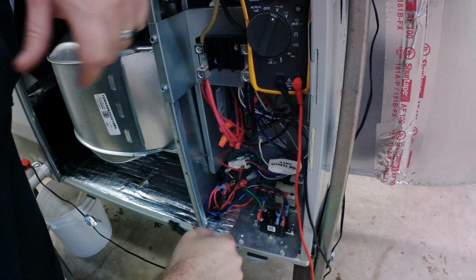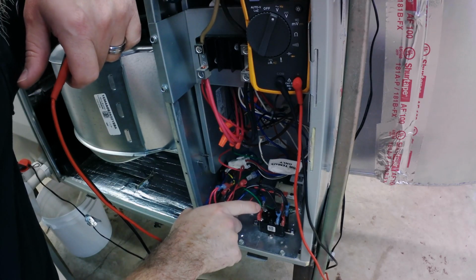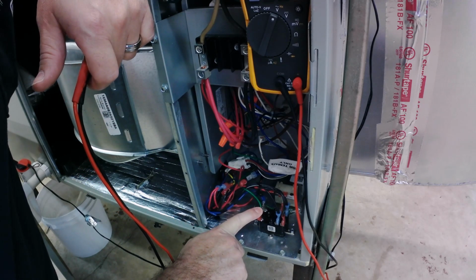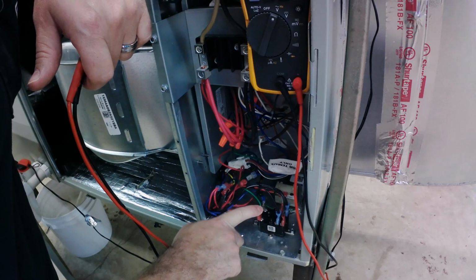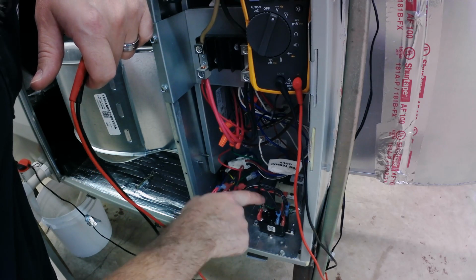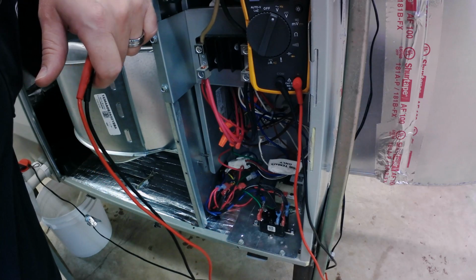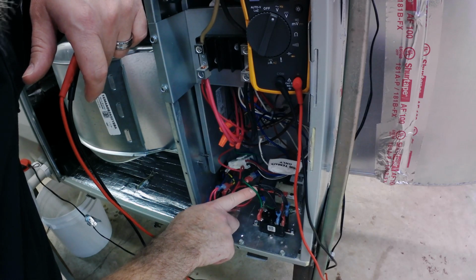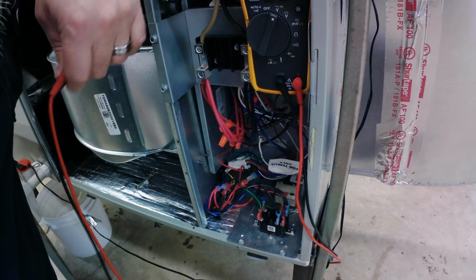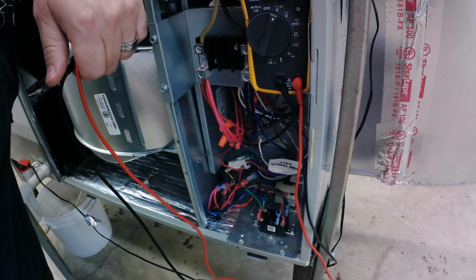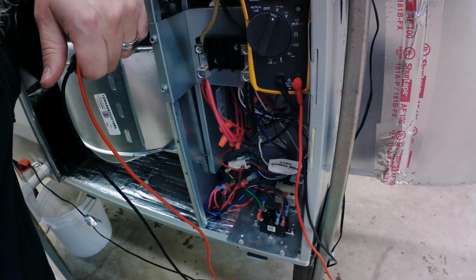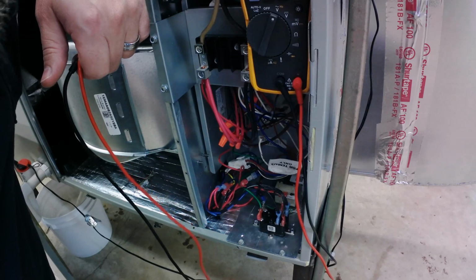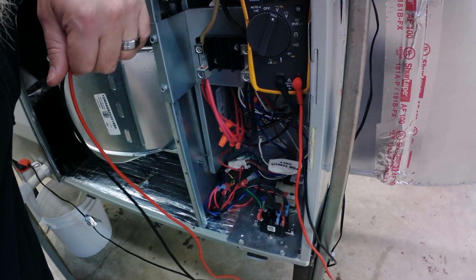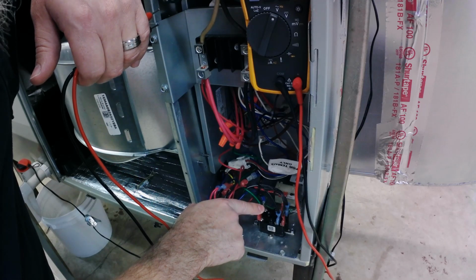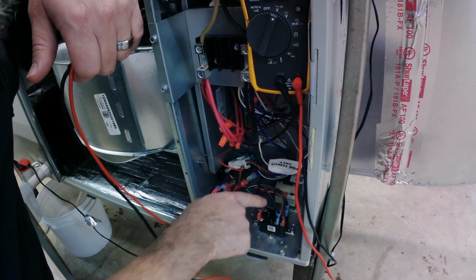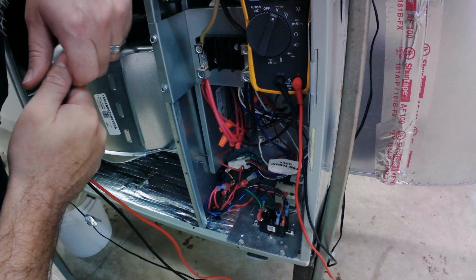Now, one thing I'll tell you too is if you have voltage to the coil, then the thermostat's not the problem. If you don't have any voltage here on your 24 volt connections to that coil, then don't blame the relay yet. You need to troubleshoot and find out where your 24 volts went, in this case on the G circuit. But if it's a contactor, you would make sure that if you don't have 24 volts on the contactor coil, then you would of course need to maybe troubleshoot low pressure switches or a float switch or something of that nature. But if voltage is there, then we're going to ohm out the coil if needed. If it's not there, then we're going to backtrack in the wiring and find out where the voltage went.